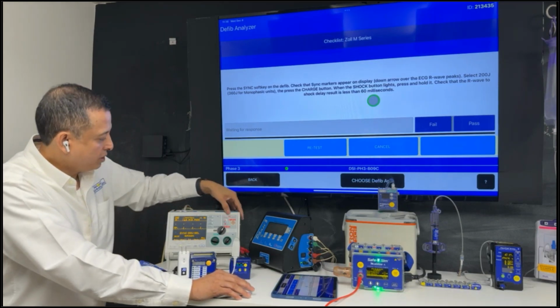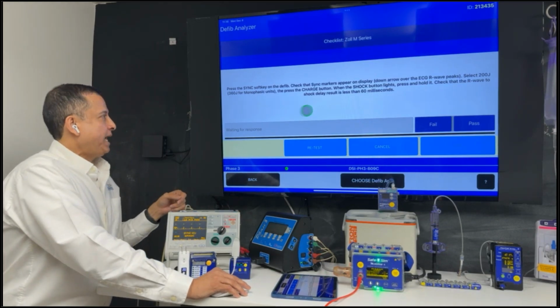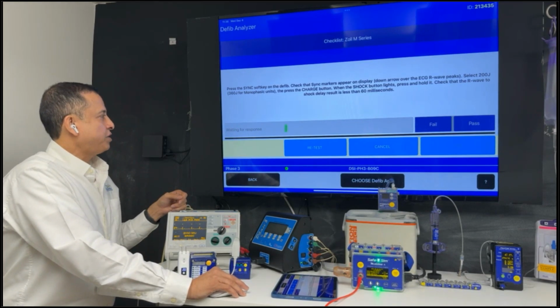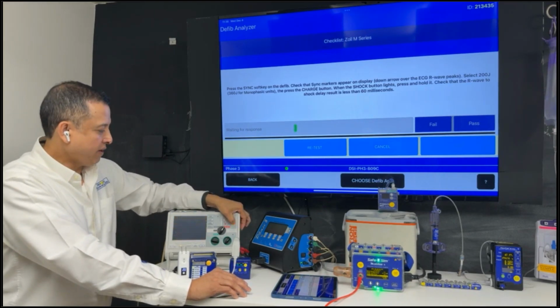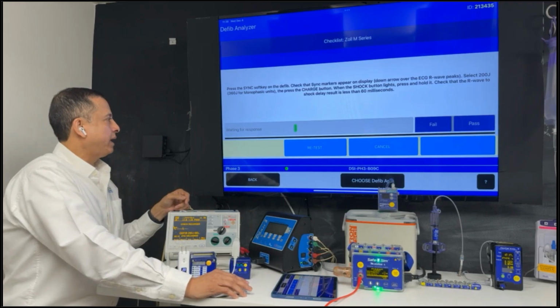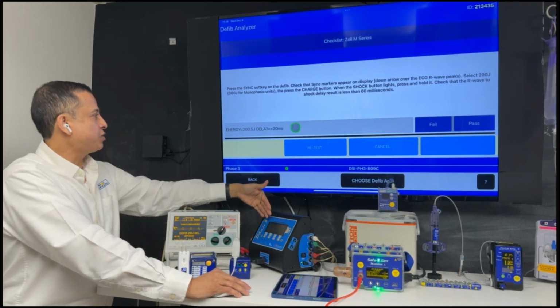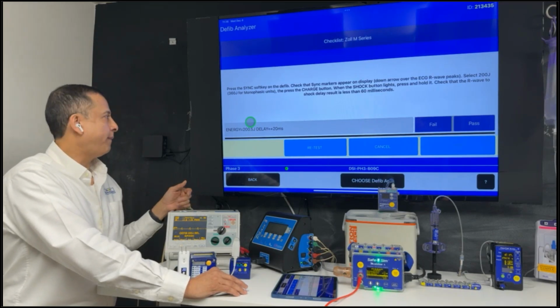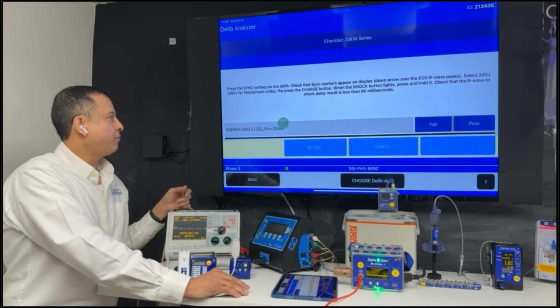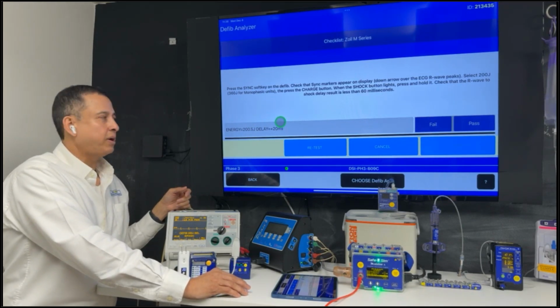So I'm going to go ahead and charge it. And then what we're waiting for in this gray box here is for the analyzer to make the measurement and report back the result. So I'll go ahead and fire it. And the analyzer is making the measurement, it decides the result, and it brings back the joule discharge amount in joules. And then more importantly for this test, what was the sync delay?